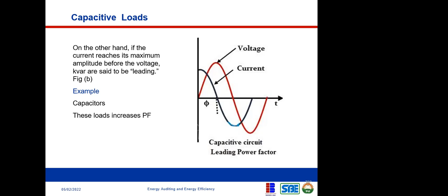Remember, an inductive load reduces power factor, but a capacitive load increases it. So ideally, if you want to correct the problem of an inductive load reducing power factor, you need to add capacitors to the system. As a way of correcting power factor, we introduce capacitor banks. That's why in industry, wherever you want to correct power factor, you introduce capacitors.